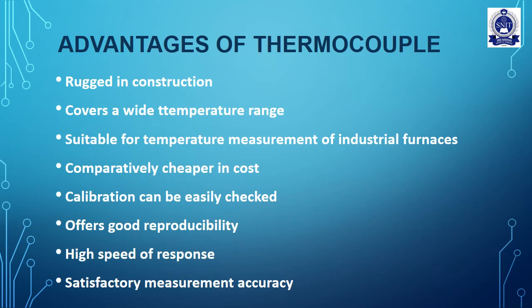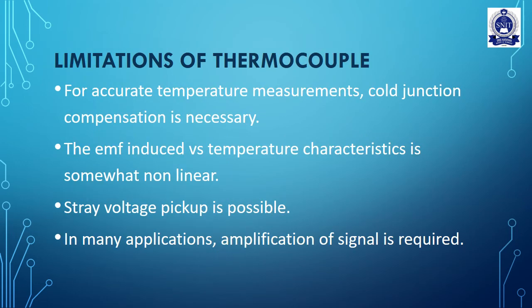The main advantages of thermocouple are: it is rugged in construction, covers a wide temperature range, suitable for industrial temperature measurement, comparatively cheaper in cost, calibration can be easily checked, and it offers good reproducibility, high speed of response, and satisfactory measurement accuracy.